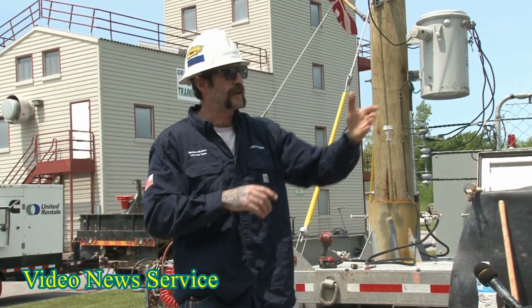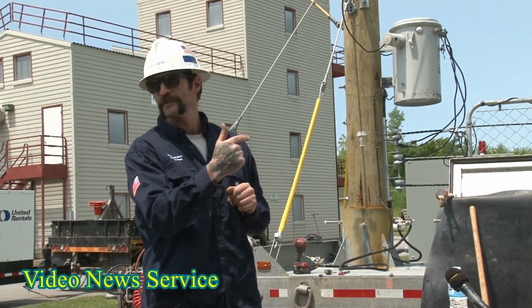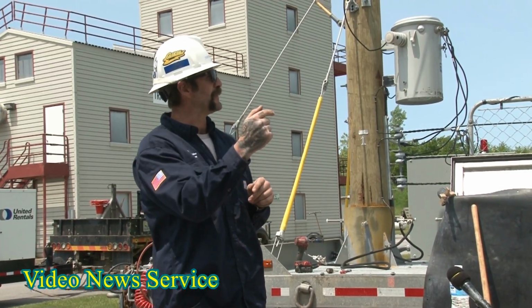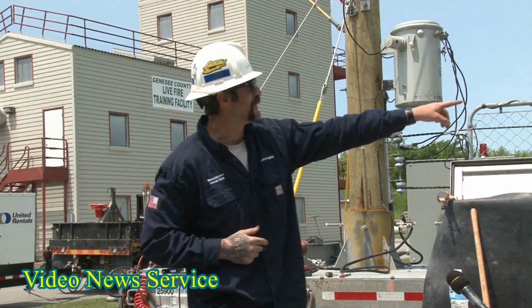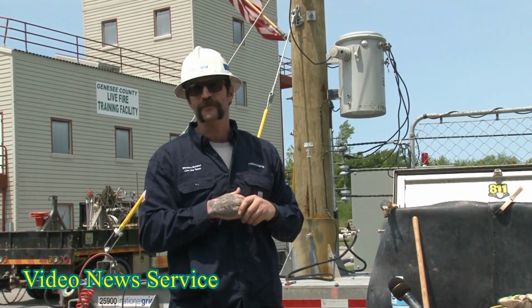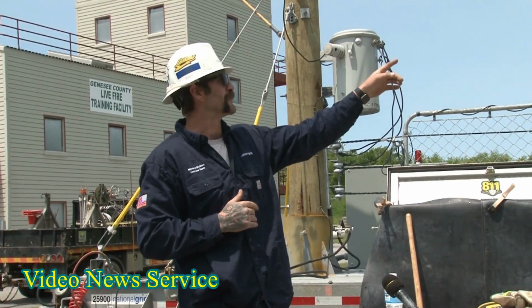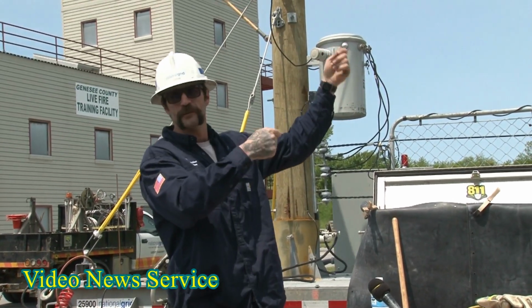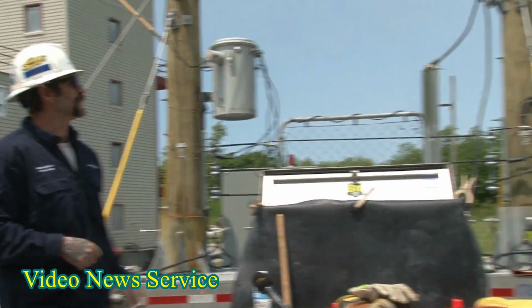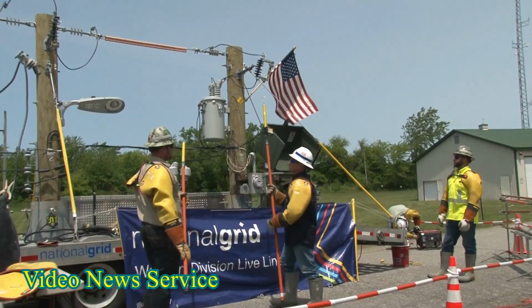And then we're going to show you how when you wire a generator, say you run it right into your panel box, and if you do not turn your main breaker off, you're actually backfeeding through your panel box, through your meter channel, up into that transformer, and that transformer is taking that 120, 240 volts and stepping it up to 4,900 volts, you will see. And if you guys get a close-up, you'll see it on the phaser. So just go ahead, show them 0 volts on there now. Actually, you can turn the generator on and show them the 0 volts, and then we'll turn that breaker on.